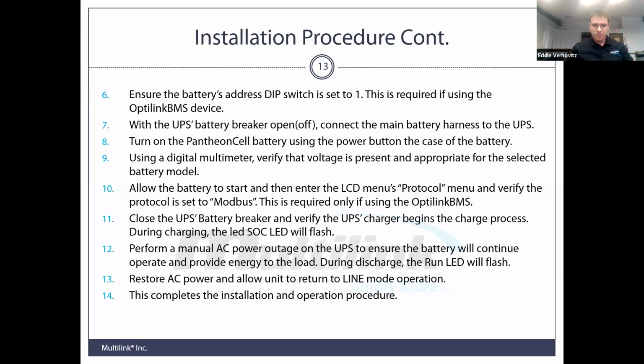So moving on to step 10, after we've allowed the battery to start, the UPS is now up and running, and the LCD menu has become available. We want to enter the protocol menu and verify that the protocol is set to Modbus. Again, this is only required if you are using the Optilink BMS.